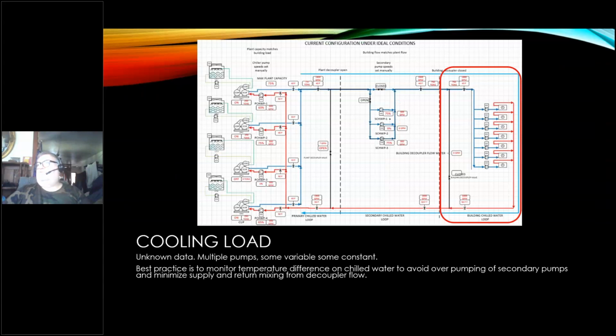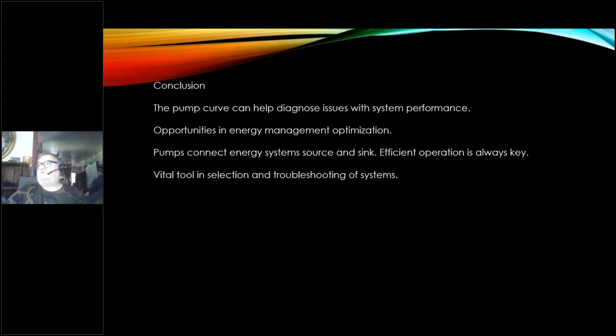Now, the real unknown I've got at this point is the building. Okay, so it's got multiple pumps, all different sizes. Some of them are variable, some of them are constant. I've got to really watch what's going on. So in order to defeat this or to manage it, we watch the water temperature coming back out of the building. So we operate the central plant based on a temperature difference that comes out of the building. As long as I match my flow out of the plant with the flow on the secondary into the building, I can maintain a temperature difference across my plant without having to fully automate my building. That's the next step. But it's mainly derived to maintain a constant differential temperature.